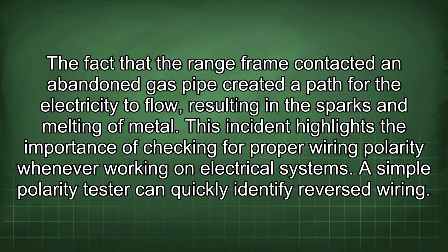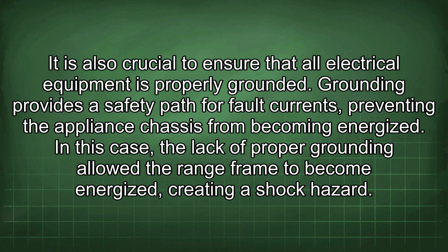This incident highlights the importance of checking for proper wiring polarity whenever working on electrical systems. A simple polarity tester can quickly identify reverse wiring. It is also crucial to ensure that all electrical equipment is properly grounded. Grounding provides a safety path for fault currents, preventing the appliance chassis from becoming energized. In this case, the lack of proper grounding allowed the range frame to become energized, creating a shock hazard.